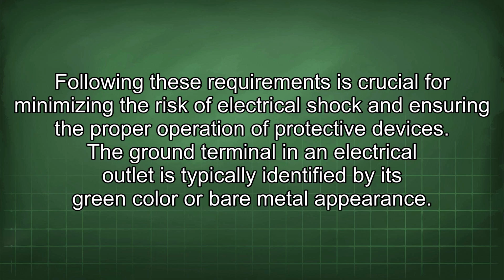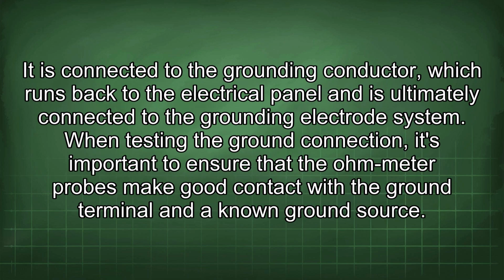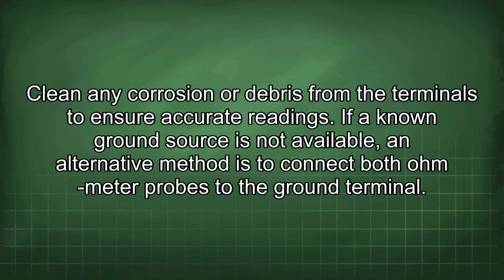The ground terminal in an electrical outlet is typically identified by its green color or bare metal appearance. It is connected to the grounding conductor, which runs back to the electrical panel and is ultimately connected to the grounding electrode system. When testing the ground connection, it's important to ensure that the Ohm-Meter probes make good contact with the ground terminal and a known ground source. Clean any corrosion or debris from the terminals to ensure accurate readings.